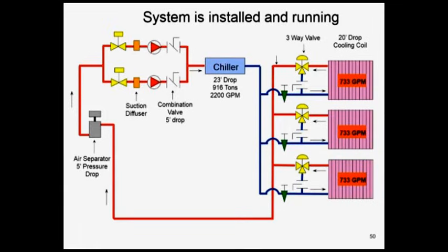I've got 2 pumps running in parallel, no big deal here, but I'm flowing at design flow per the chiller manufacturer, 2,200 GPM at 23 feet of drop. What do we know? The chiller manufacturer told us that the flow rate at design flow of 2,200 GPM had a pressure drop of 23 feet, or 10 pounds. 2.31 feet make a pound. So 23 feet of drop would be roughly 10 pounds of pressure drop through the chiller when I've got 2,200 GPM of flow. And remember what we just taught you about the square function.